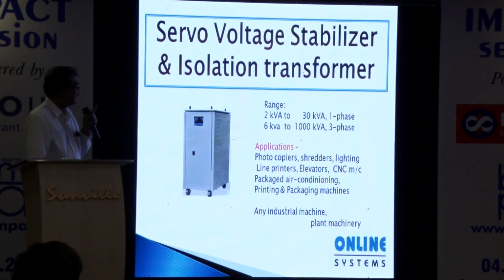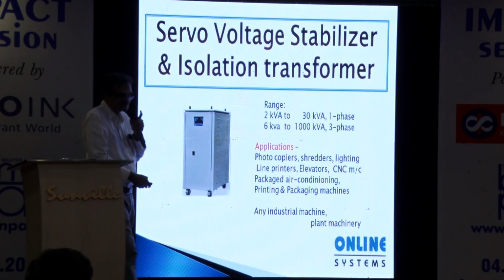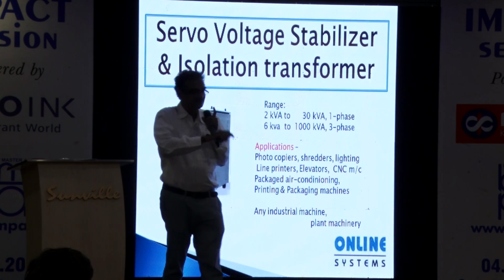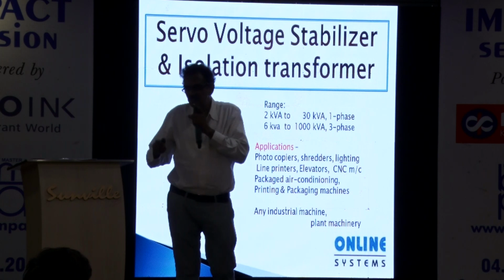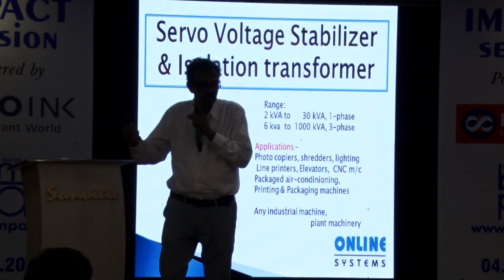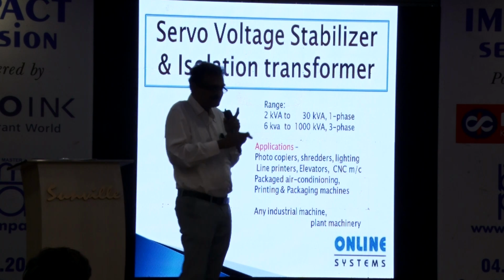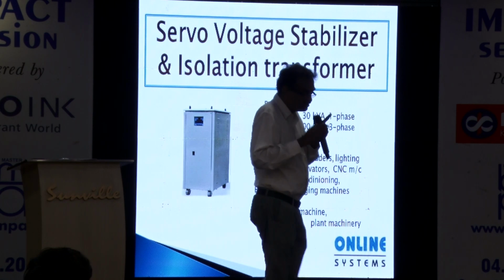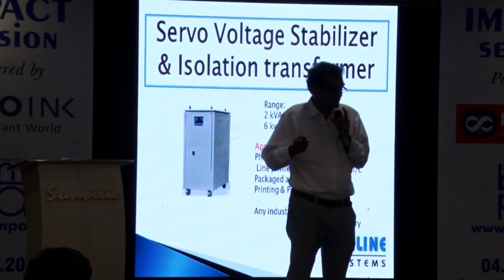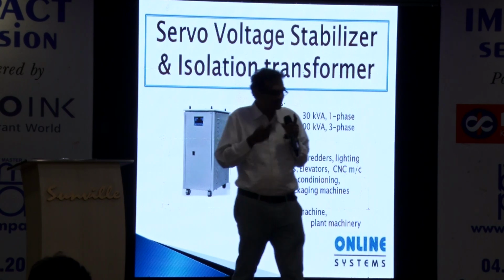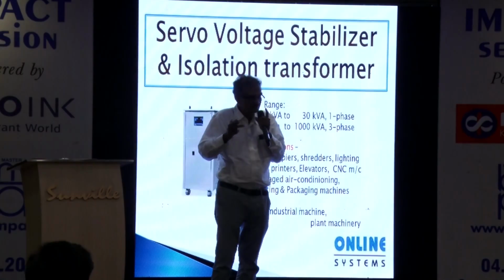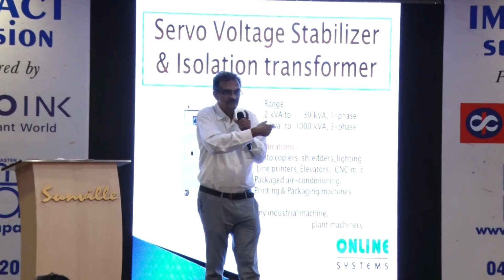Coming back, you have the typical voltage stabilizer which can take care of the bulk of the issues for most machines where too much sensitive electronics is not involved. If sensitive electronics is present and needs special protection, we have something known as a isolation transformer. Electronics works on single phase, so if I isolate that and put a isolation transformer in place, your problem is solved.